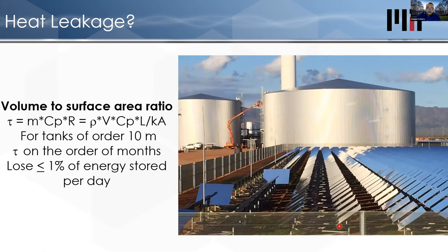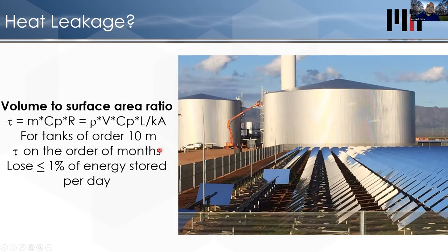If you've never thought about storing energy thermally at large scales, you might worry that the heat will just leak out — like a cup of hot coffee cooling down on a table. However, the time it takes for heat to leak out is proportional to the volume-to-surface-area ratio. So as you make a tank extremely large — on the order of 10 meters in diameter and 10 meters tall, with tens of thousands of tons of liquid salt inside — the time constant for cooling is on the order of months. You can lose less than about 1% of the energy per day as long as you're cycling the battery frequently, making heat leakage essentially negligible.